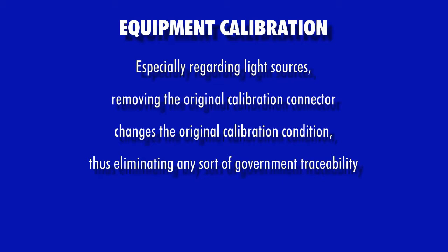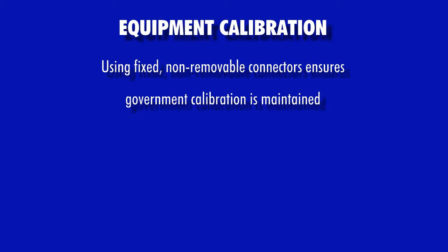If the alignment or connection of the light source port is disturbed in any way, such as with changing out an interchangeable connector, the light source is no longer in its original calibration condition. When this happens, any sort of government traceability the light source once had will be lost. Thus, to make absolutely sure proper calibration is maintained, light sources should have fixed, non-removable connector ports.